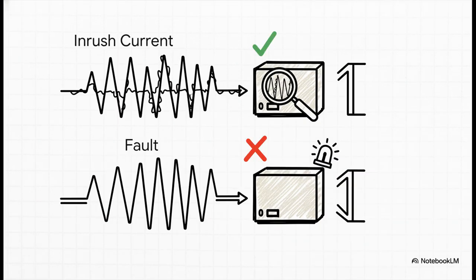And this inrush current is a perfect example of how clever these modern systems are. That huge spike of current, it turns out, has a unique electrical fingerprint. It's full of these specific distortions. Engineers call them harmonics. So the relay is basically trained to be a detective. It looks for that specific fingerprint. If it sees a huge current spike, but it also sees that harmonic fingerprint, it knows, this isn't a robbery. The owner is just opening the vault, and it holds back from tripping.